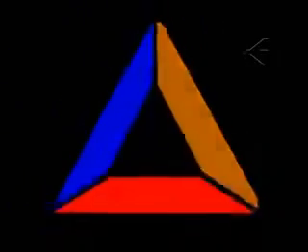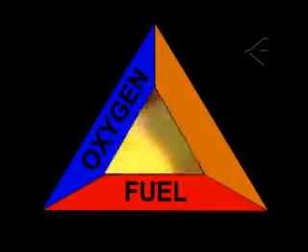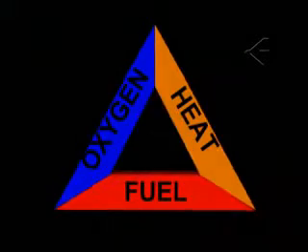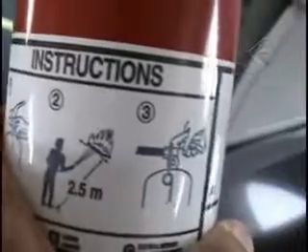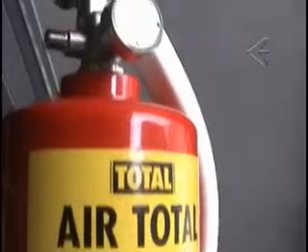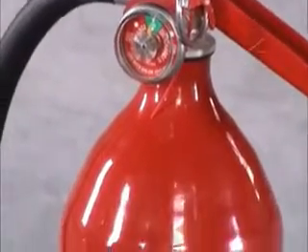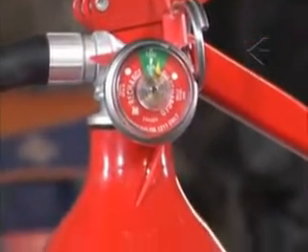Remember, a fire will go on until all the combustible material is consumed, the oxygen is used up, the temperature has been reduced, or the chain reaction has been broken. A fire extinguisher may contain a charge for an 8 to 25 second spray, depending on the make and model of the extinguisher. Have backup extinguishers available to use after depletion to continue the firefighting effort.